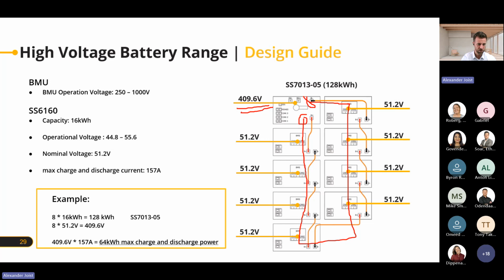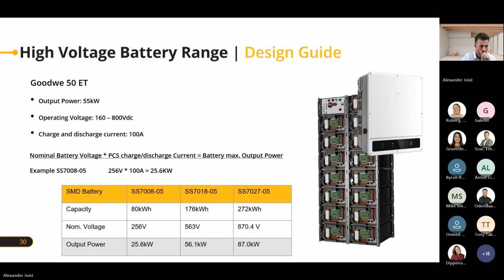If we now look into the calculations of that, we take 8 times 16, so we have 8 battery modules, which is 128 kilowatt hours, our SS7013. Then we take 8 times 51.2, we have 409 volt. And now the 409 volt multiplied by 157 amps gives us a total of 64 kilowatt of maximum charge and discharge power. So this is the maximum the battery can give. If we now compare that with the inverter, let's take the GoodWe 50 for instance. The GoodWe 50 output power is actually 55 kilowatts maximum charge and discharge power, a little bit higher, 10% higher than what it says on the nameplate.